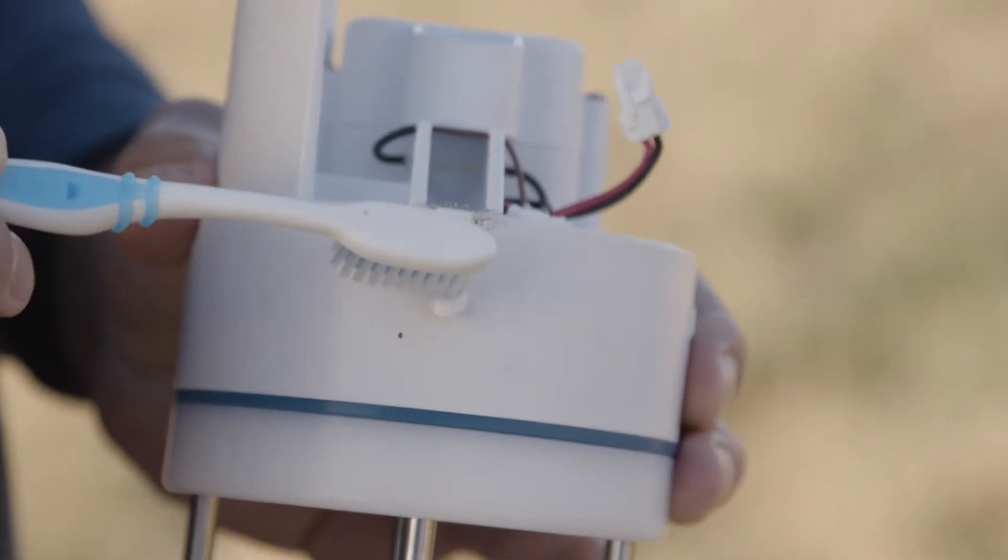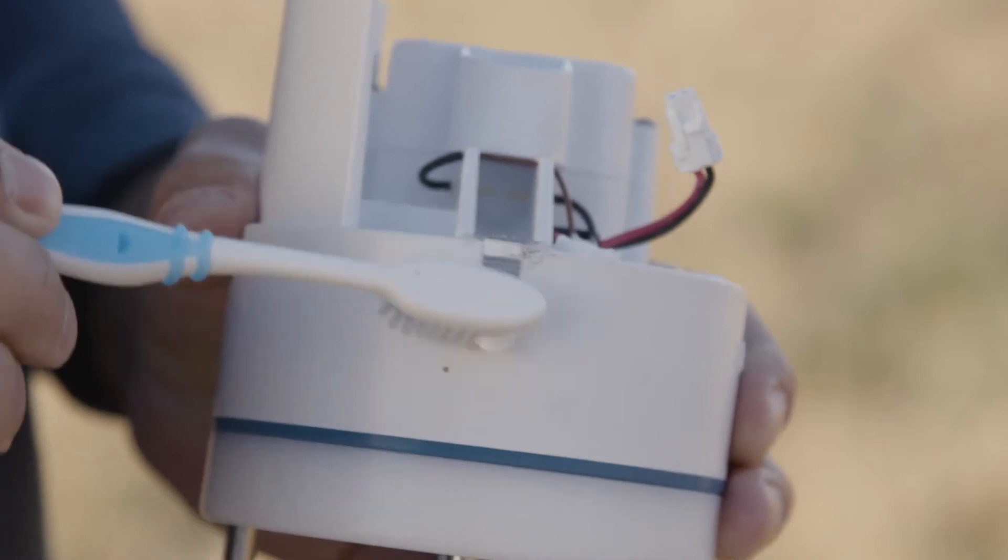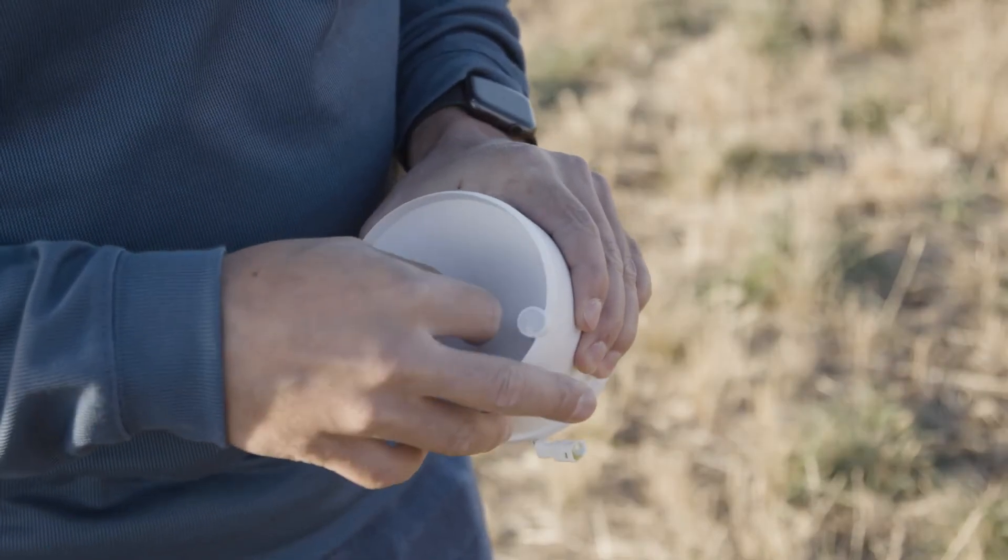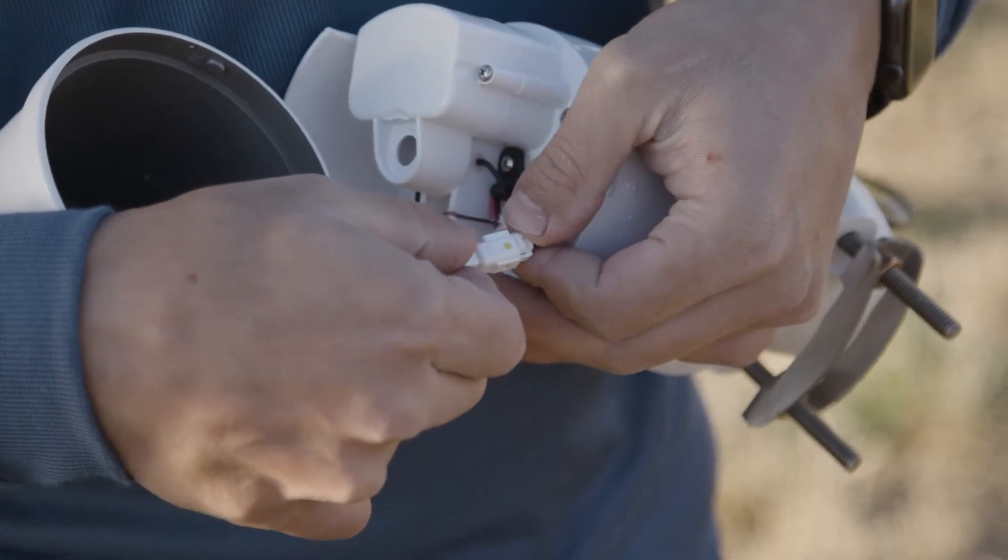Clean the screen using a toothbrush. After cleaning is complete, reattach the springs, the pyranometer cable, and the funnel.